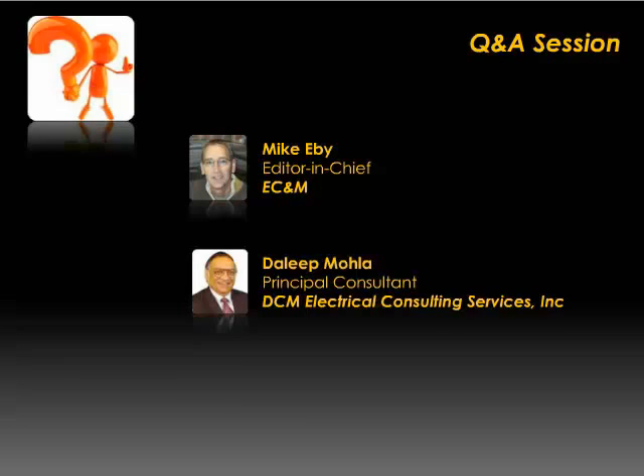Okay, so back to the questions. One of them has to do with, I've got a person who says, I have a 277-volt lighting system. How do I take advantage of a high-resistance grounded system in that situation? Okay, this is a very common question, because looks like in the 60s and 70s design was done that you have a very large transformer solidly grounded and you try to use lighting from one phase, 277.